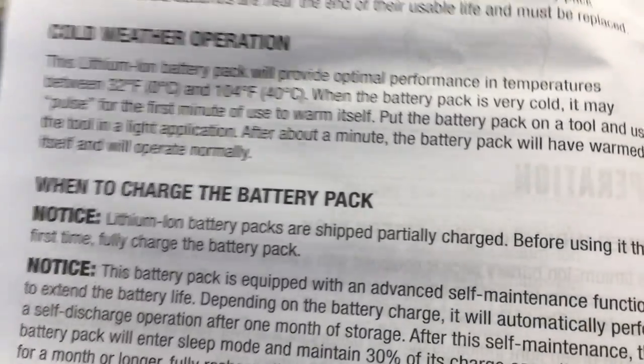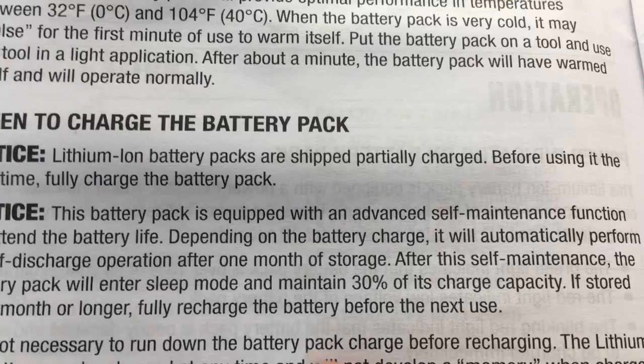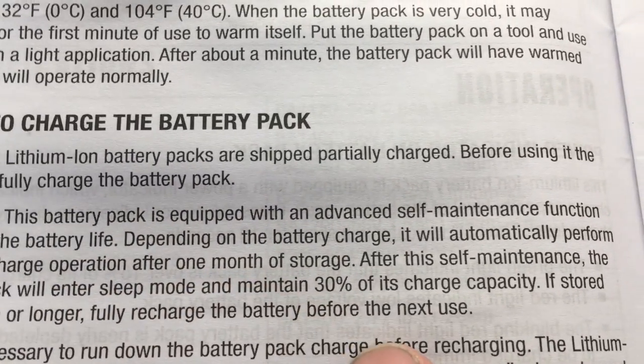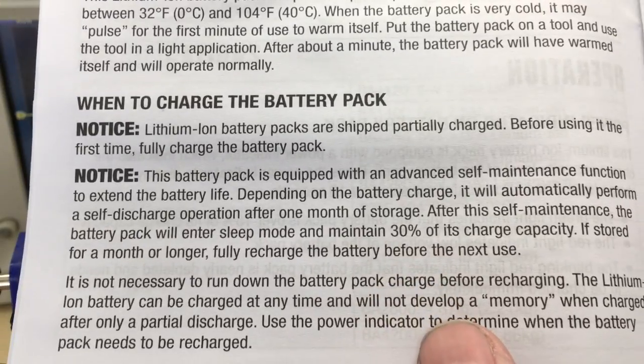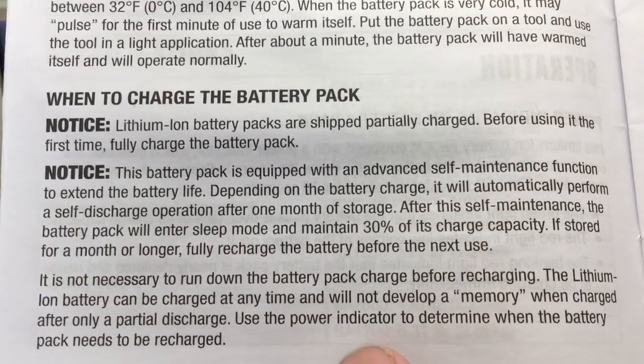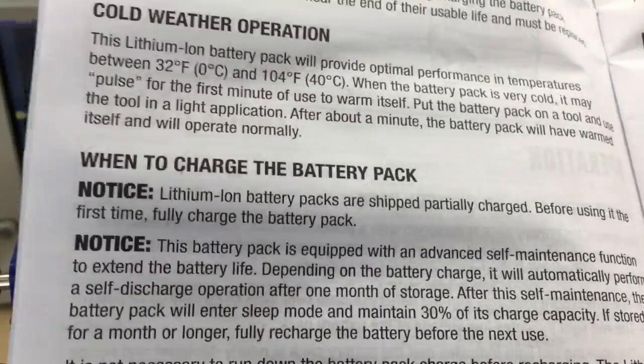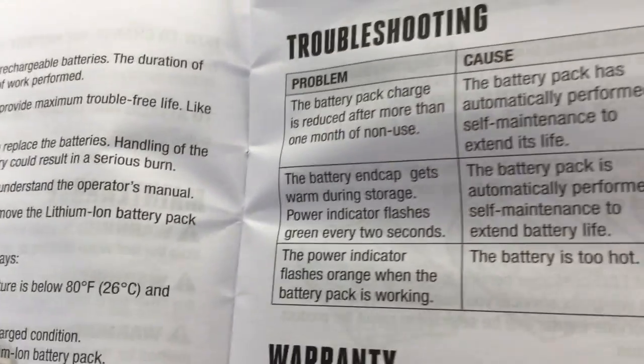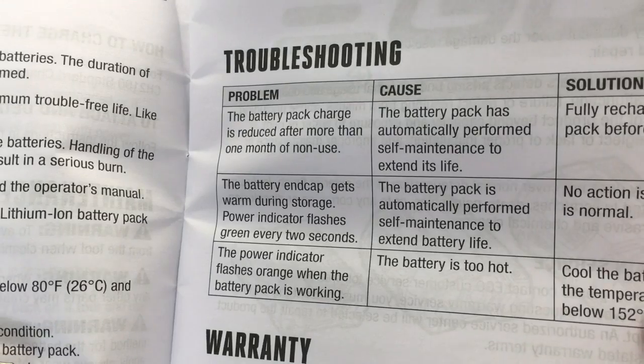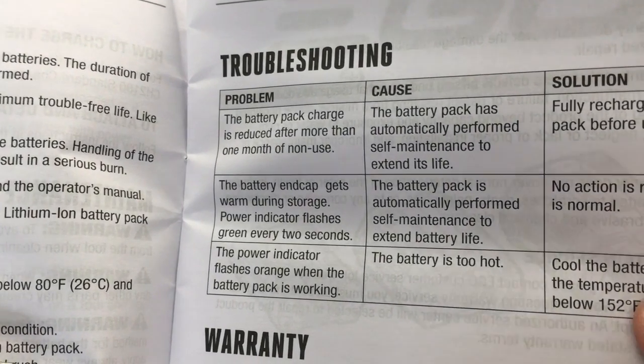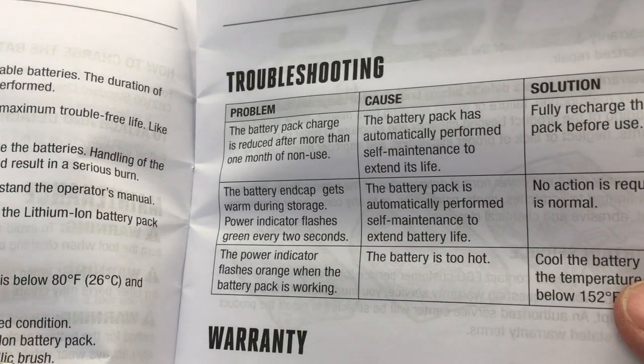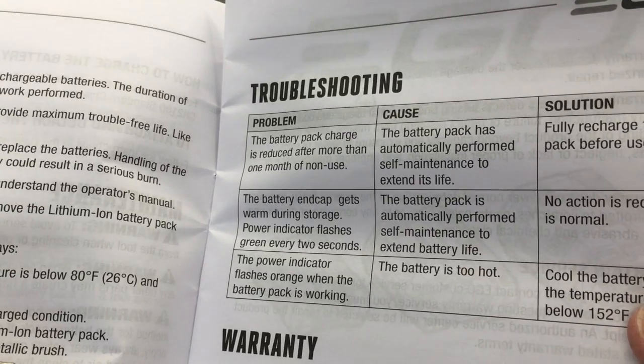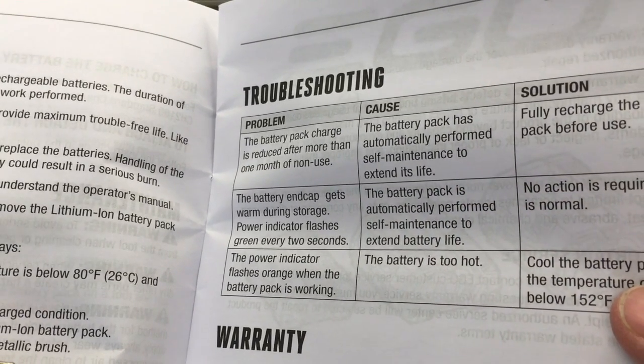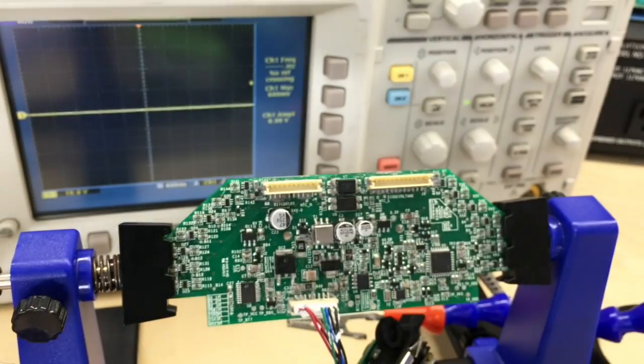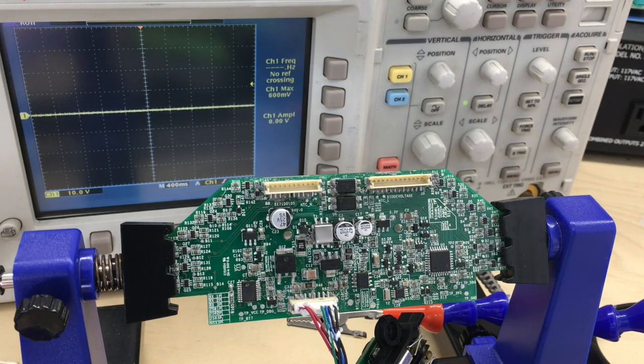It does talk about the pack and charging. It does mention that it will self-discharge after 1 month of storage. That it'll go to what they call a sleep mode and maintain 30% of the charge capacity. So it doesn't mention there that it blinks green while that's happening. It does, however, mention under troubleshooting the battery end cap gets warm during storage, which is what's going on with this, and the power indicator flashing green every 2 seconds, which it ain't quite 2 seconds either, but it doesn't mention that anywhere else. It just says that it's actually in a self-maintenance mode, but evidently it will pull the battery down to 0, so there's something going on there.